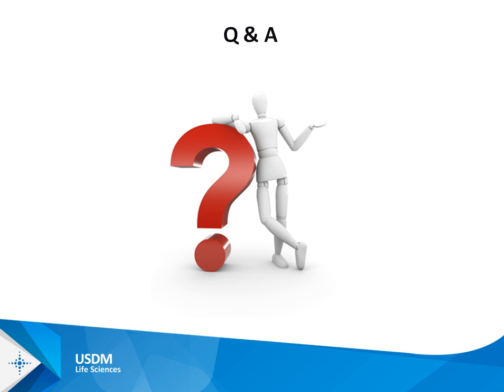Thank you, Jay. Bill is asking if you can elaborate on UDI requirements and timeline for software that is installed on equipment such as generators and pumps, etc. So UDI doesn't apply to software, firmware if you will, that's embedded in a device. The UDI only applies to what we call standalone software, so a piece of software that is itself a medical device. It does not apply to software that is used to, say, run a device like a pump.